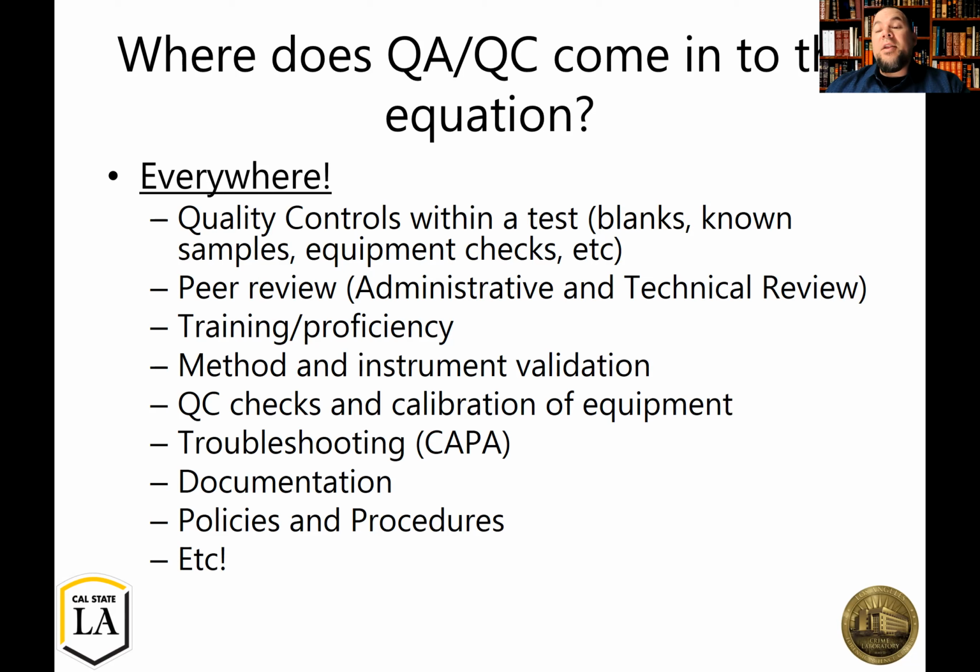So you get a brand new instrument in the laboratory, you can't really do casework on it right away. You have to spend a lot of time making sure that instrument can perform as you say it can perform, and all that needs to be documented and cataloged in the instrument validation. That takes a lot of time and effort, and that's something that Danny loves to do. But that's a huge part before you can take that instrument into casework. So you've got to do a lot of work ahead of time.